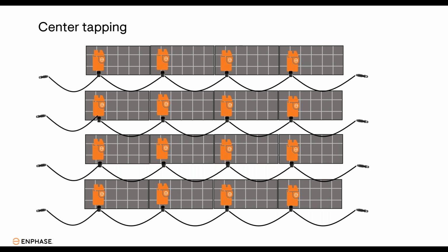Voltage rise can be a concern. So Enphase recommends that you keep your voltage rise at less than 2%. All of the QD cabling options come with center tap connectors already built into the QD cable. Like on the previous slide, I mentioned that there are 120 connectors on a length of QD cable. After every 6th connector that is meant to have a microinverter plugged into it, there is a center tap connector already built into that cable. That center tap connector is required to be used on any circuit that's larger or longer than 6 microinverters. And this will reduce that issue of voltage rise.